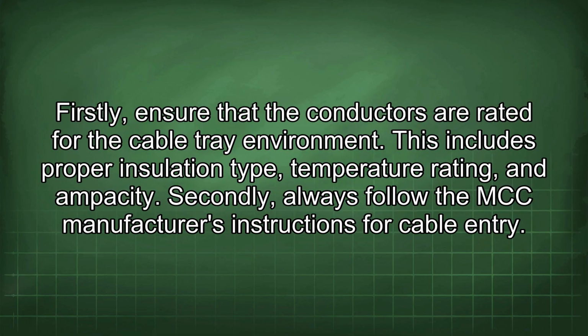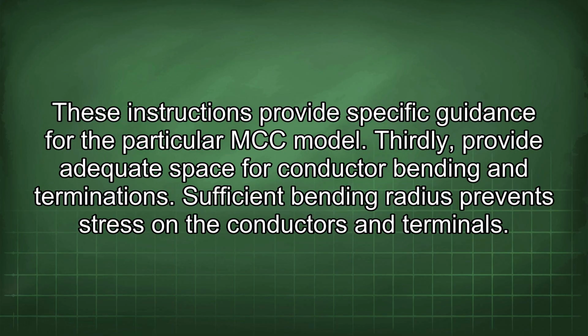Firstly, ensure that the conductors are rated for the cable tray environment. This includes proper insulation type, temperature rating, and ampacity. Secondly, always follow the MCC manufacturer's instructions for cable entry. These instructions provide specific guidance for the particular MCC model.